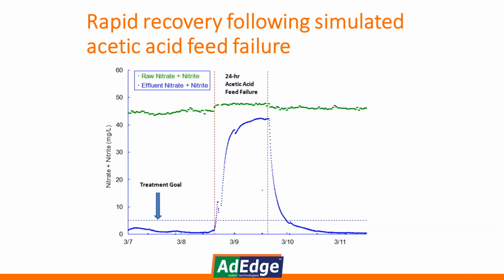In many of the tests, we do what's called an acetic acid failure test. This is just done to demonstrate that you do need the acetic acid and the nutrients being fed in for proper operation. We certainly have controls in place so that if something were to happen with an acetic acid pump, the operator would be alerted immediately or very quickly based on nitrate readings from monitors, and they would be able to go back there and see if they lost prime or something happened to one of the pumps.